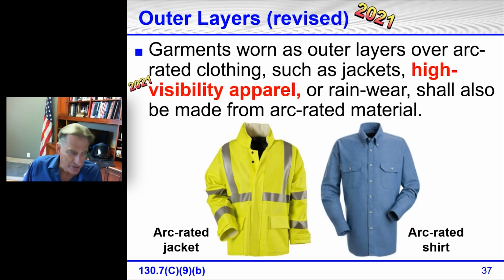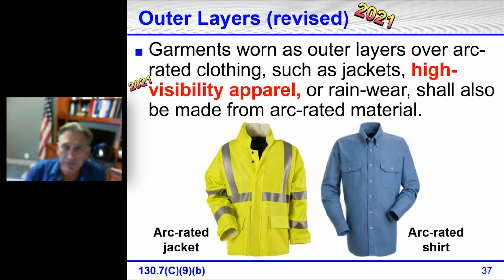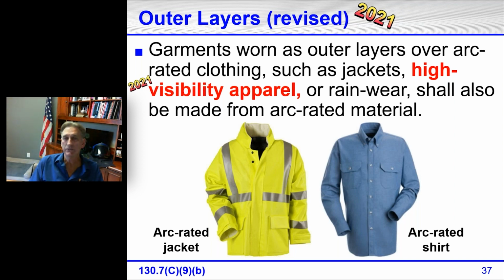A couple more changes in the 2021 edition. Garments worn as outer layers over arc-rated clothing, such as jackets, and they added high visibility apparel or rainwear, should also be made from arc-rated material. So the outerwear also has to be made from arc-rated material. This is a Bulwark rain jacket that is arc-rated. Until we were going over the changes to make the 2021 edition of 70E, I was always under the assumption that whatever was on the outside had to be equal to or greater than the incident energy of the equipment you're standing in front of.